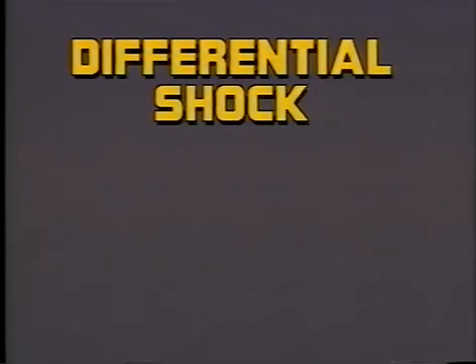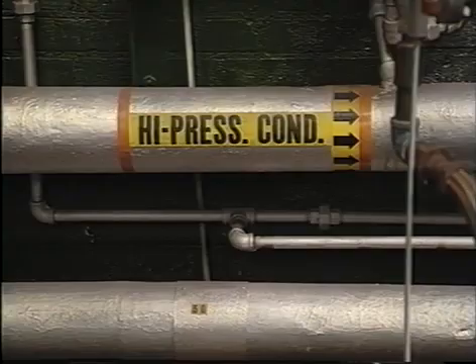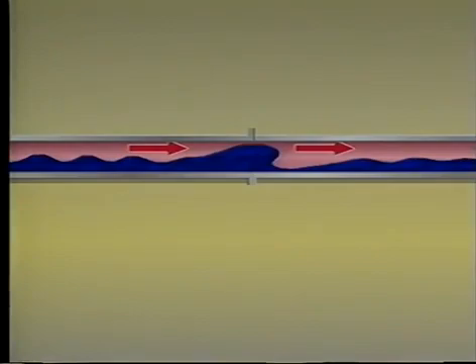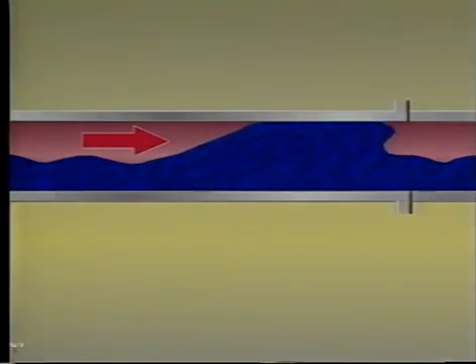Differential shock, like thermal shock, occurs in biphase systems. Differential shock can occur whenever steam and condensate flow in the same line, but at different velocities, such as in high pressure condensate return lines. In biphase systems, the velocity of the steam is often ten times the velocity of the liquid. If this gas flow causes condensate waves to rise and fill the pipe, a seal is formed with the pressure of the steam behind it. Since the steam cannot flow through the condensate seal, pressure drops on the downstream side. The condensate seal now becomes a piston that is accelerated downstream by virtue of this pressure differential. As it is driven downstream, the piston picks up more liquid that is added to the existing mass of the slug and velocity increases. This is differential shock.